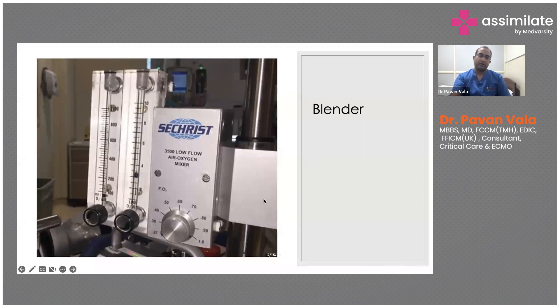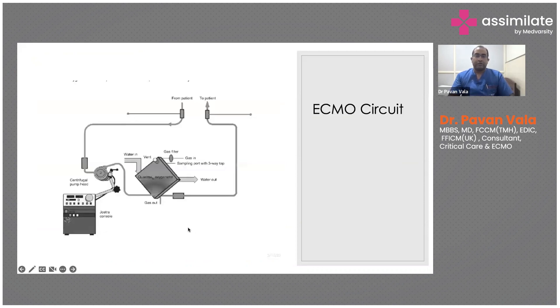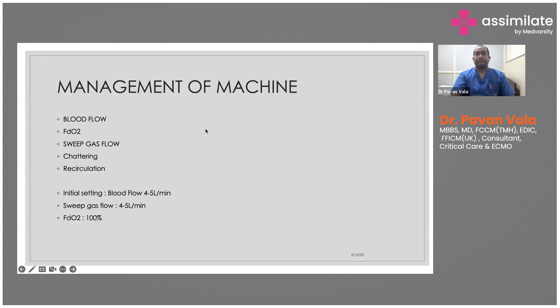There is a blender to achieve gas flows and set the FDO2. Putting all these elements together, the basic circuit is: blood comes from the patient, goes through the centrifugal pump, then through the oxygenator, and returns back to the patient.